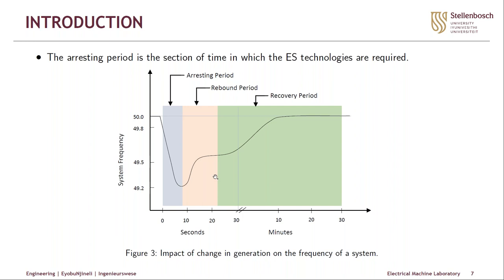Figure 3 shows the impact of a generation loss on the frequency of a system. As the frequency decays, we have an arresting period of less than 10 seconds, a rebound period of 10 to 20 seconds, and then a recovery period. Under primary response, systems are required to respond in less than 10 seconds in order to capture this decay in frequency. The system should also be capable of handling over-frequency events.